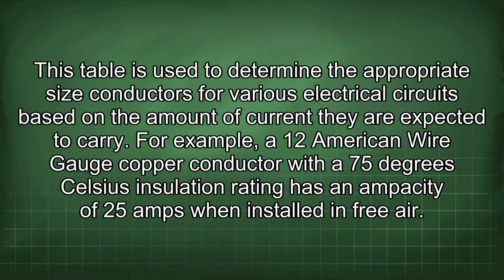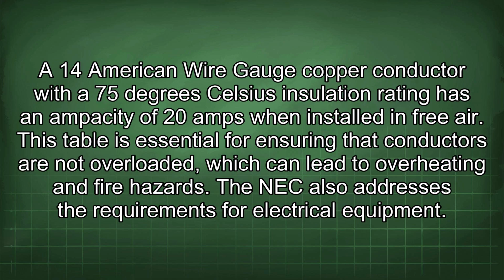For example, a 12 American wire gauge copper conductor with a 75 degrees Celsius insulation rating has an ampacity of 25 amps when installed in free air. A 14 American wire gauge copper conductor with a 75 degrees Celsius insulation rating has an ampacity of 20 amps when installed in free air. This table is essential for ensuring that conductors are not overloaded, which can lead to overheating and fire hazards.